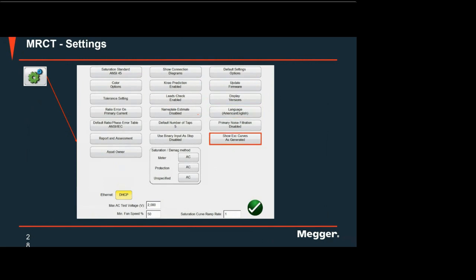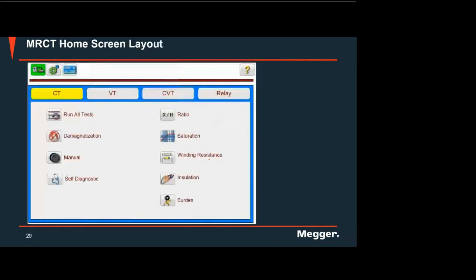it has, of course, the option to change whether your saturation and demag shall be done on AC or DC. According to the standard, you can do both AC or DC. If you do DC, then your testing will be faster because you are saturating in a much faster way. Unlike on AC, if you do it at nominal frequency, then your saturation or excitation curve test will take longer. All right, so you can select AC or DC. Of course, some other equipment uses AC at a very, very low frequency to make it faster. But with us, we have the option to use AC or DC.